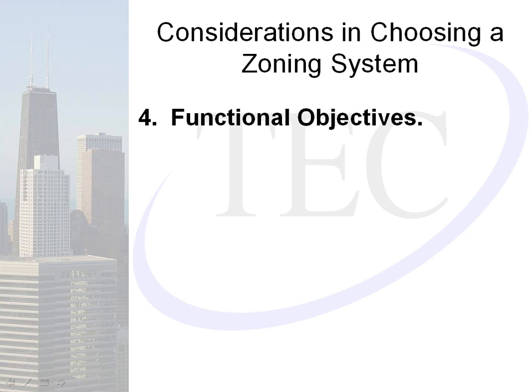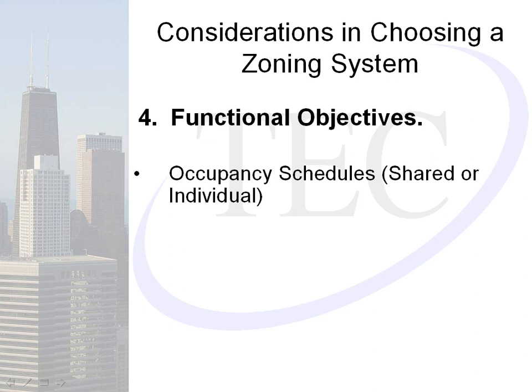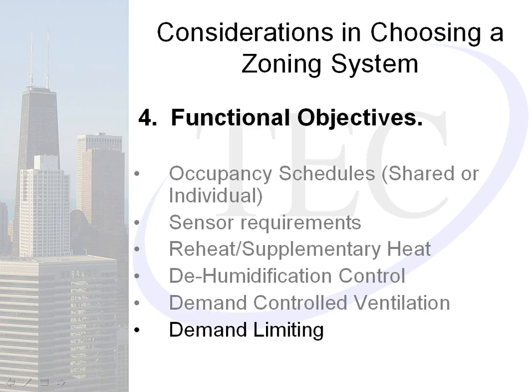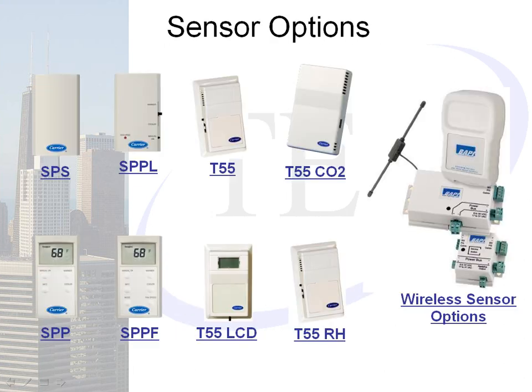The fourth consideration is functional objectives — things like occupancy schedules, shared or individual sensor requirements, reheat or supplementary heat, dehumidification control, demand control ventilation, demand limiting, and tenant billing. There are a variety of sensor options available: communicating sensors, plain temperature sensors, sensors with slide bars, digital display models with true set point adjustment, and advanced options such as CO2 sensing for demand control ventilation, relative humidity sensors for dehumidification control, and wireless sensor options.